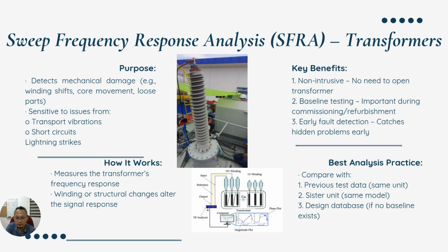Now, let's talk about sweep frequency response analysis, or SFRA. SFRA is particularly useful for detecting mechanical damage such as winding shift or core movement, which can occur due to transport vibration, short circuits, or lightning strikes. The great thing about SFRA is that it is non-intrusive. There's no need to open the transformer to perform the test. By measuring the transformer's frequency response and comparing it with baseline data or similar units, SFRA allows us to detect hidden problems early.